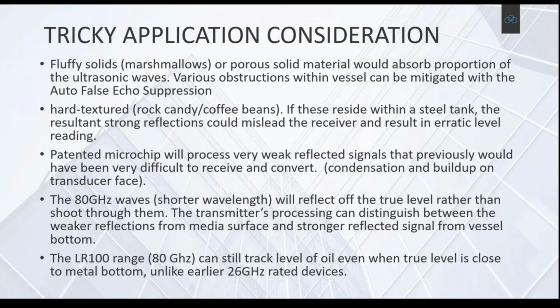So it would just be too powerful, be overkill, and hit the bottom, which gives a hard signal because it's a steel tank, and it can only reflect up - it can't pass through that, but it would pass through the oil before. With the 80 gigahertz, with the shorter wavelength, it's a bit more nuanced - a surgical incision rather than using a blunt hammer, which was 26 gigahertz. So it reflects off the true level rather, even if it lies close to the bottom where it would receive that hard echo anyway. This is why 80 gigahertz you'll see, not just with Siemens but with competitors, championed as sort of the gold standard now.